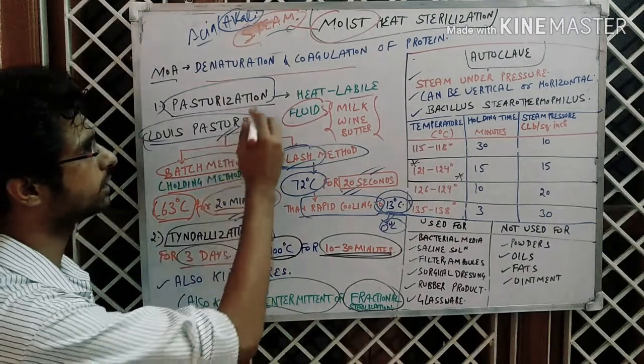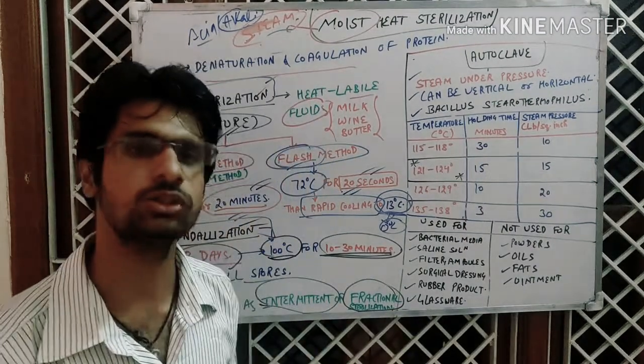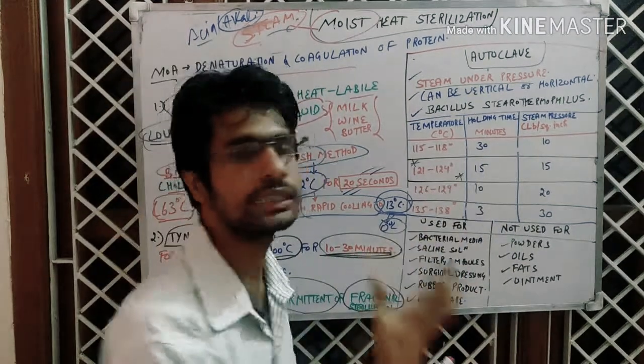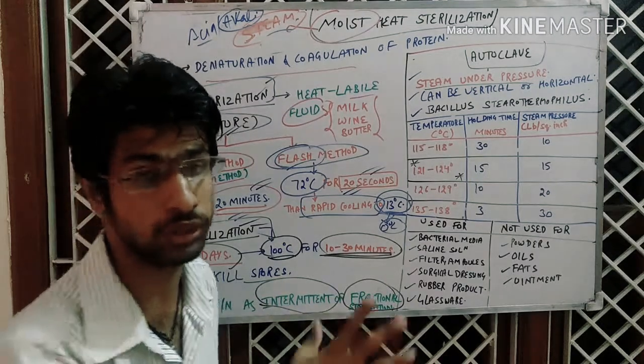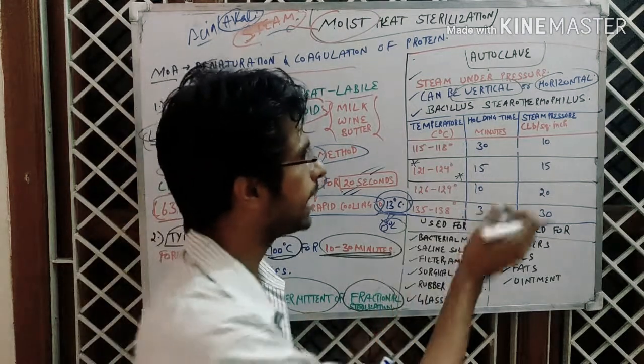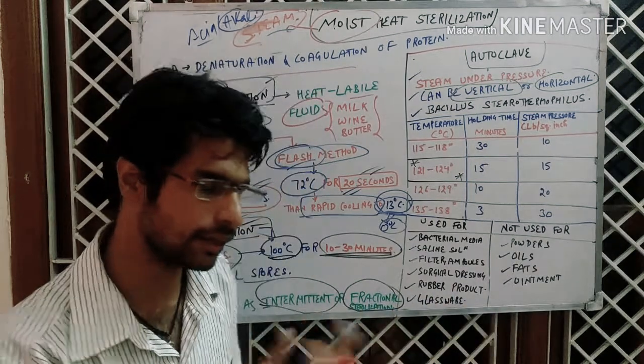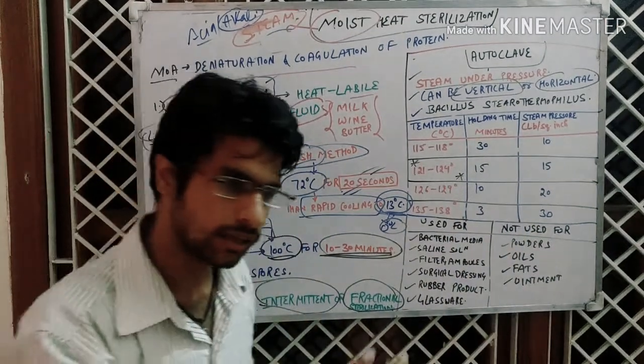Next we come to the laboratory instrument: the autoclave. You can take the pressure cooker as a simple example. It is steam under pressure — just like in a pressure cooker, steam penetrates more deeply. The autoclave can be vertical or horizontal. In industry both are used. The choice between vertical and horizontal depends on the quantity of material to be sterilized: if the quantity is more, we generally use horizontal; if less, we use vertical.